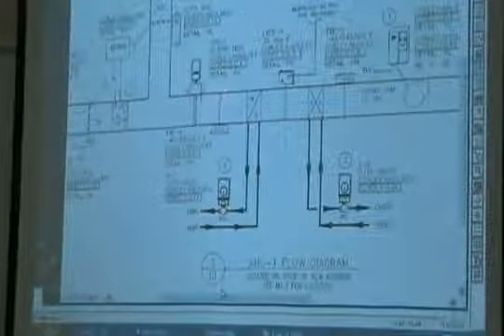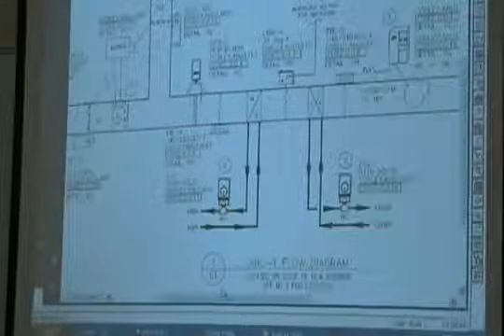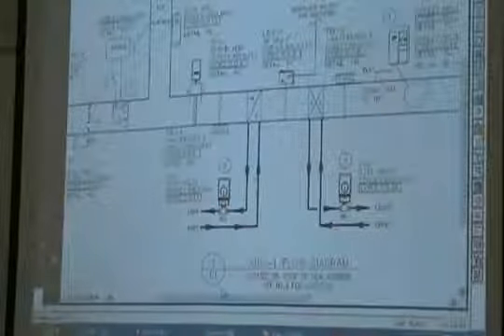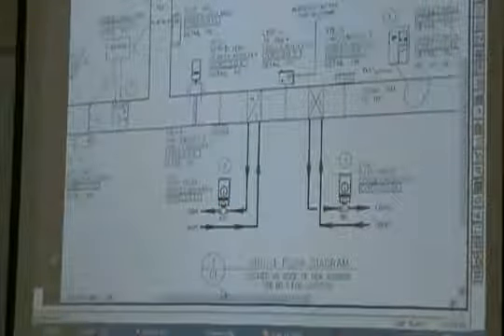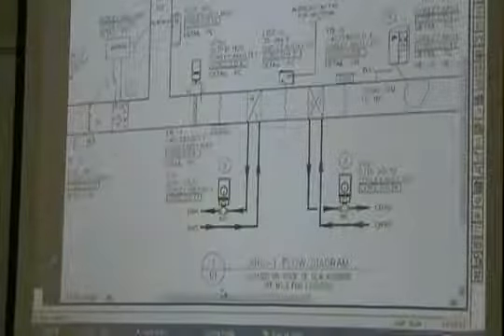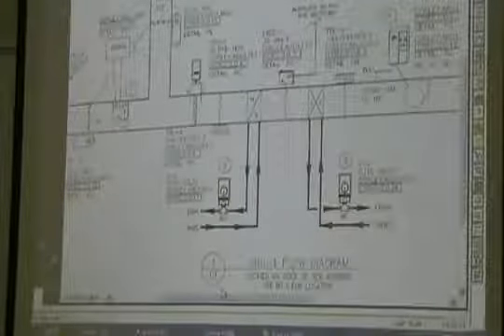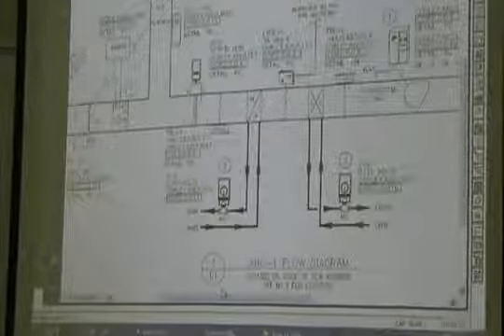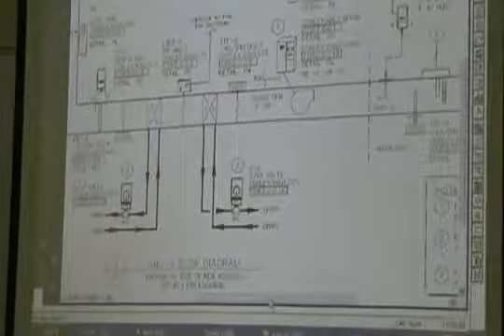Okay, another temp sensor. This now is our mixed air temp sensor, because we're mixing our return air from this path and our outside air from this path. So this is our averaging mixed air temp sensor. Thomas, what would be the point of that TD5 mixed air temp? This one right here. For me, just information. Make sure the water's working like it needs to work. Because what he's saying here is if we've got this temp sensor over here that we're going to control with, what's the purpose of this one? What would be the difference in these two?